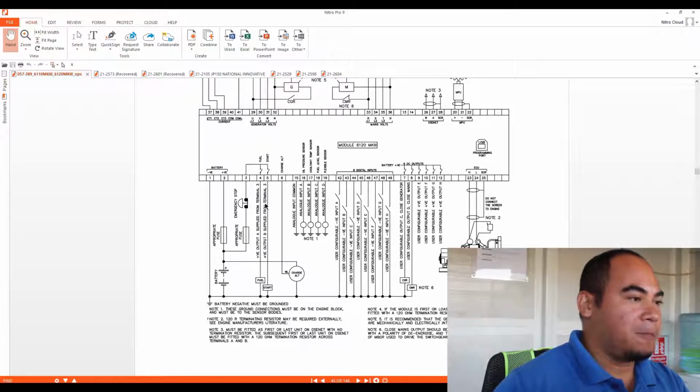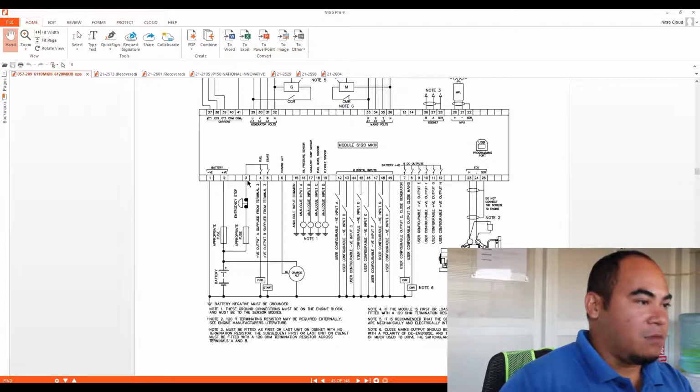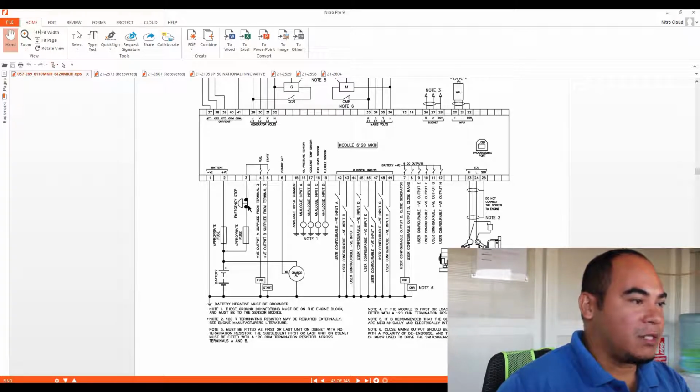Okay, so that's why here in the 4, this has an internal switch which is connected to our emergency stop in case there is some emergency problem. Once the emergency stop is pushed, directly the positive supply of your fuel and your start will be disabled, meaning there is no positive output because it is open here.